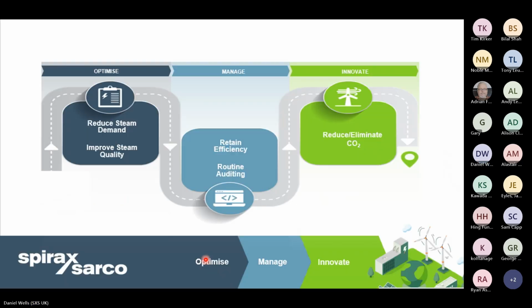to be. So coming back to that first slide, as I've mentioned, it could well be that our client is producing 10,000 kilograms of steam per hour today, when in actual fact, they've only got a requirement for 7,000 kilograms of steam. So the first thing that we want to do is ensure that the boiler is not working harder than it needs to. We're keeping our gas consumption to an absolute minimum, our cost of steam to a minimum, and our carbon emissions to a minimum.